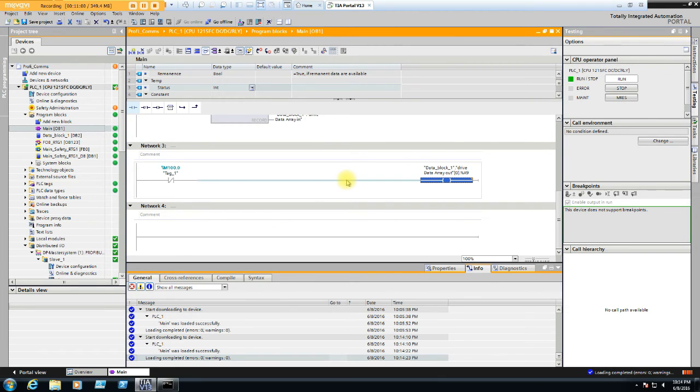I've had this argument with numerous programmers who have spent, in some cases, days saying that the drive isn't listening, that the connectivity isn't working. And I said, did you set bit 10 like I said before you even started? Oh, no, I'm going to do that later. I set bit 10. They realize they've wasted days.